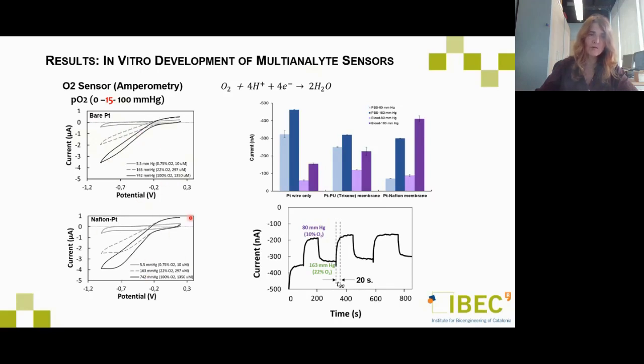And also, we modify the platinum electrode with Nafion, which has a better response. Here we checked different membranes for the detection of oxygen, and the one that gives us the better answer with standard oxygen molecules and also with blood samples is the platinum with Nafion membranes. And here you can see the repeatability of the response of these sensors with different concentrations of oxygen.